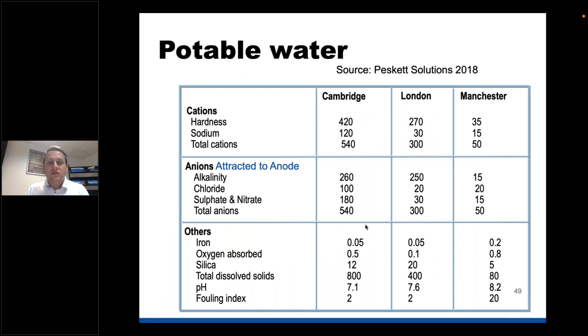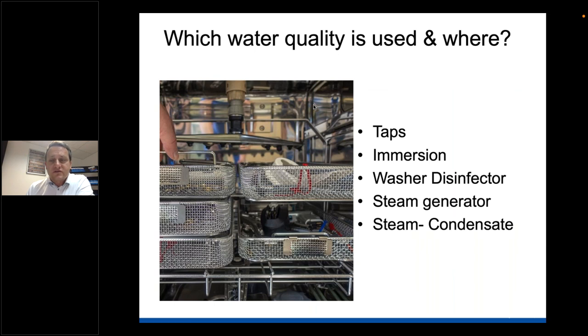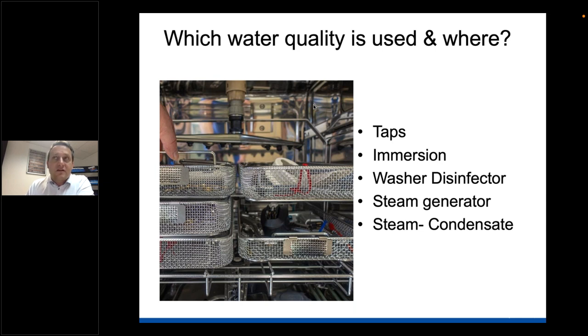For instance, Cambridge and London have very high alkalinity, and Cambridge particularly has high chloride levels - so treated water sources would be required in those hospitals to avoid damaging instruments. Water comes from many sources in a sterile services context: taps, immersion water, disinfectors, steam generators. In England, reverse osmosis water plants are generally used in theatres with treated steam to prevent water staining or mineral contaminants.